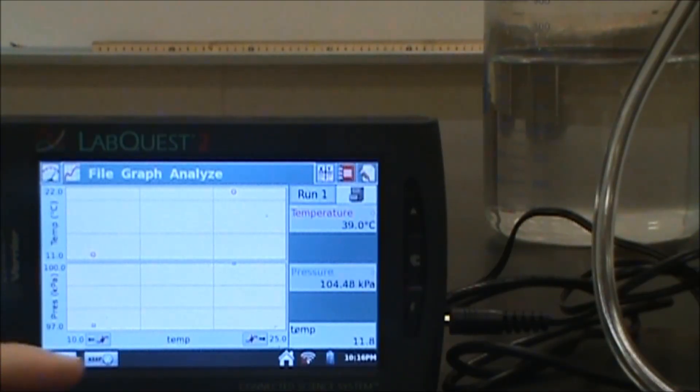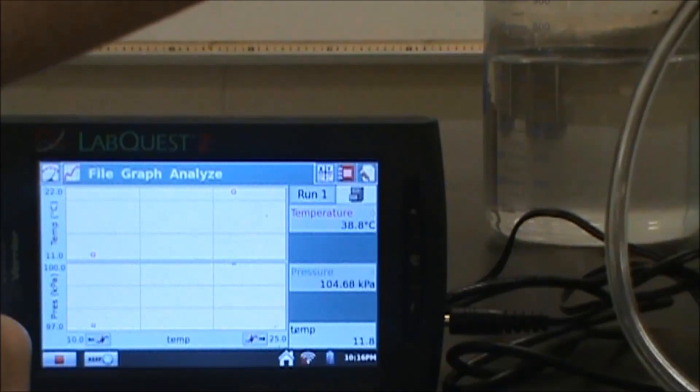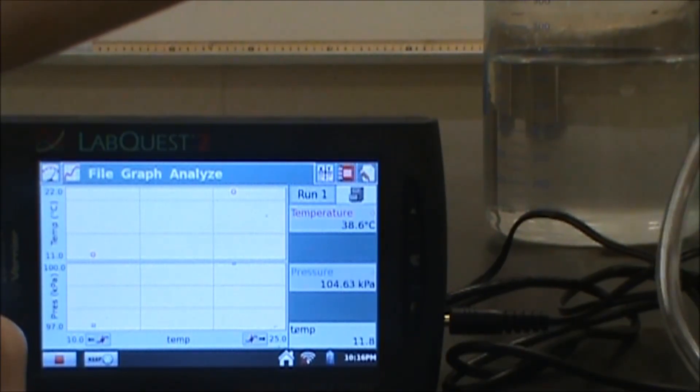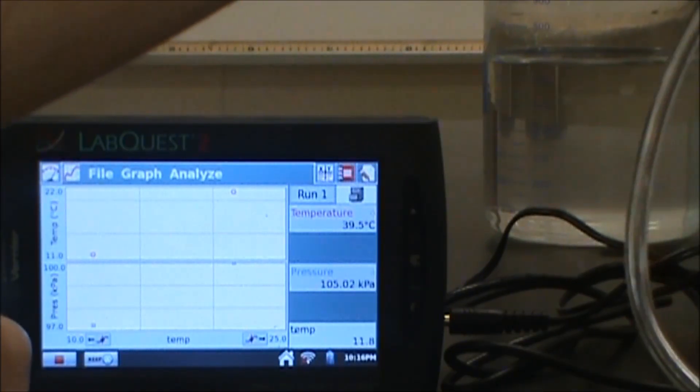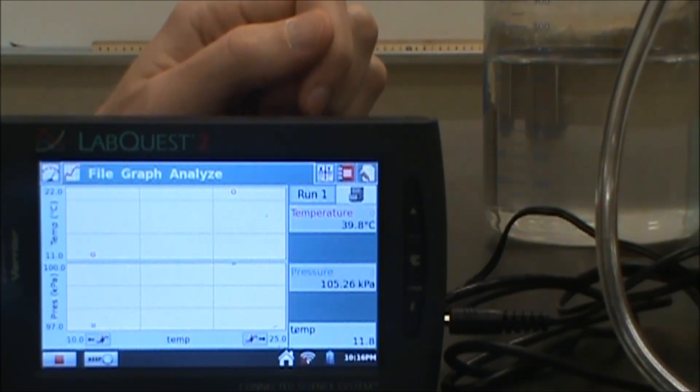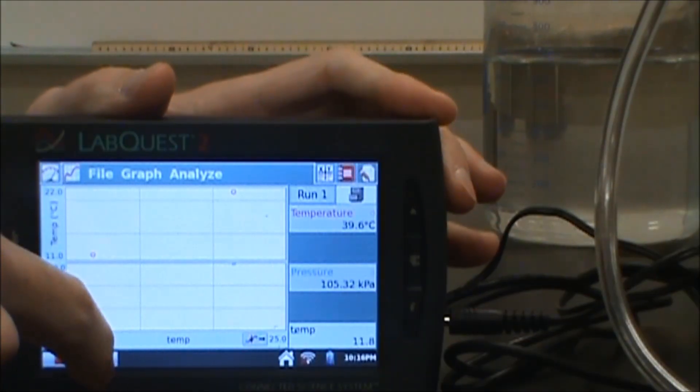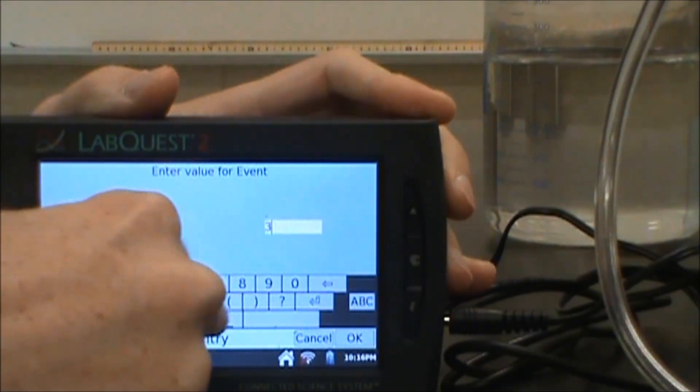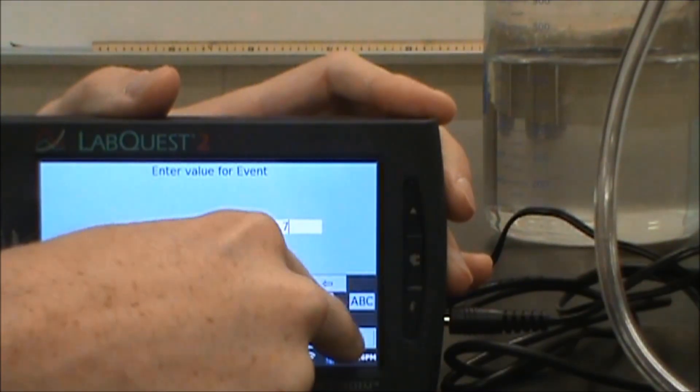When I get to that point, currently I'm showing a temperature of a little under 40 degrees. I'm going to make sure that I get as much contact with that gas inside of there as I can. Probably not quite there yet, but let's go ahead and keep. We're going to write down 39.7 for our temperature. Hit OK.